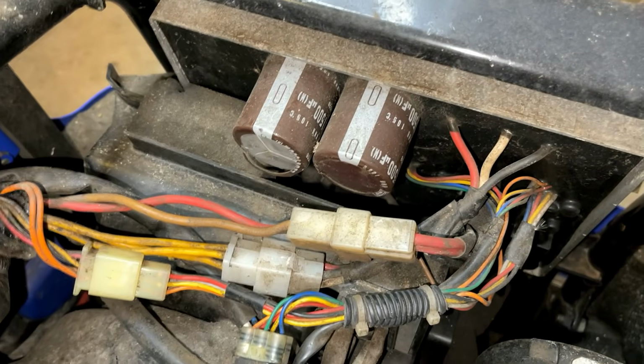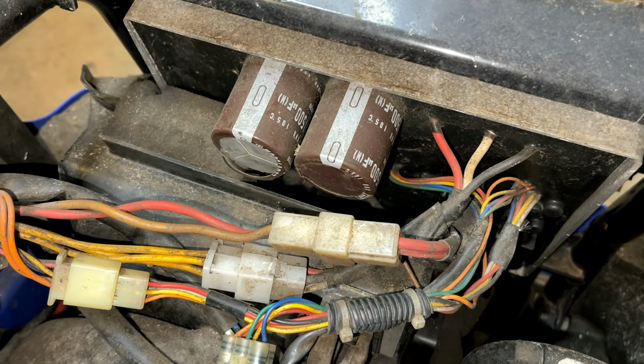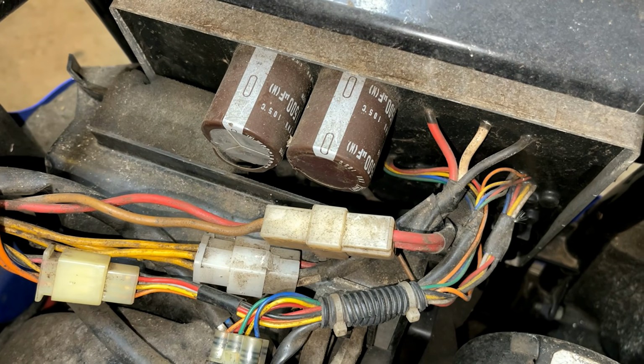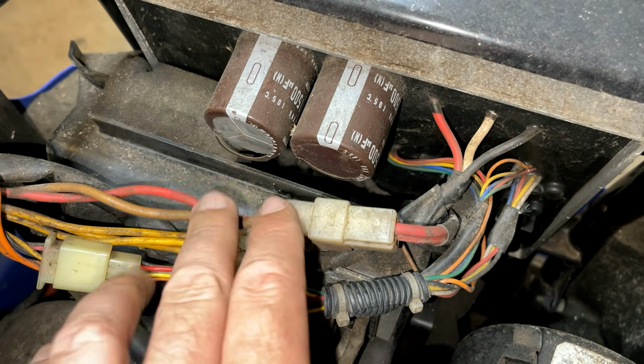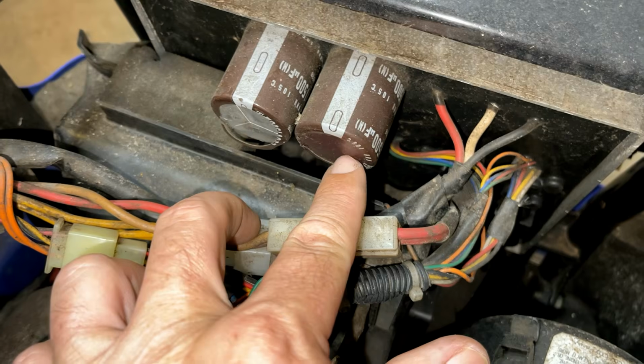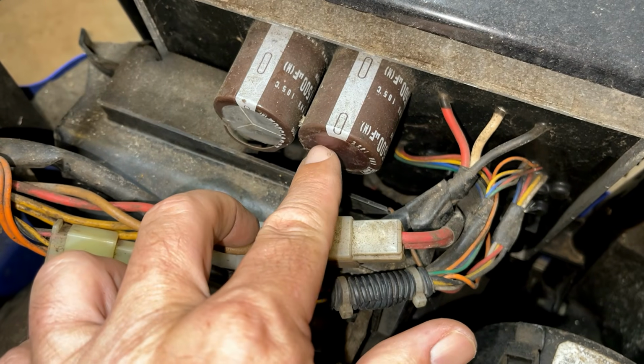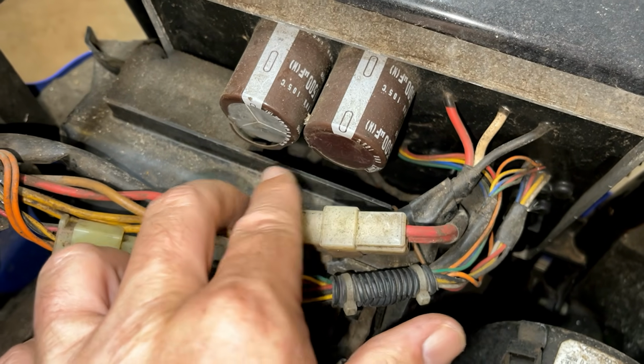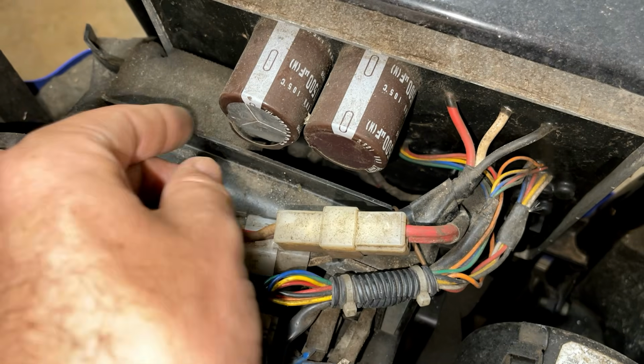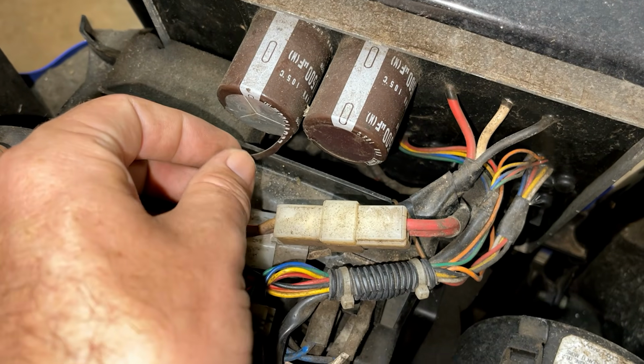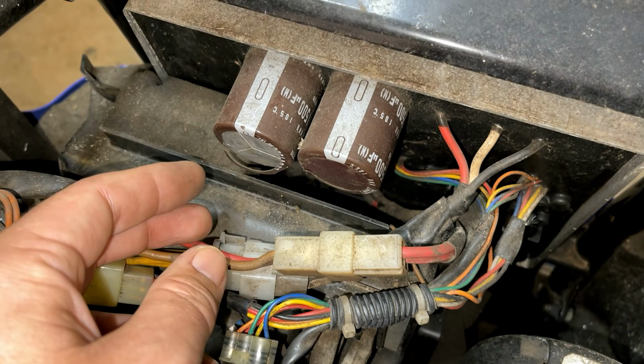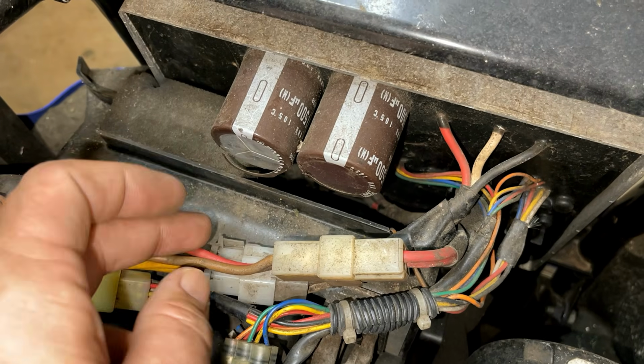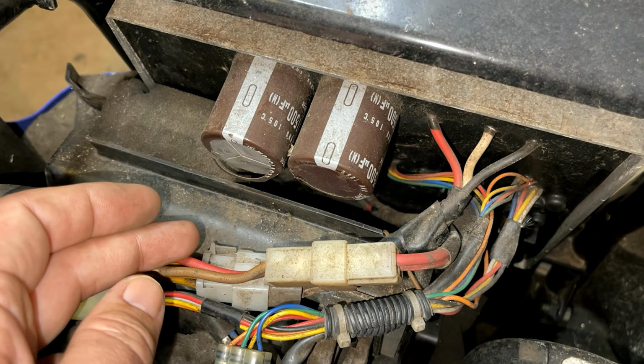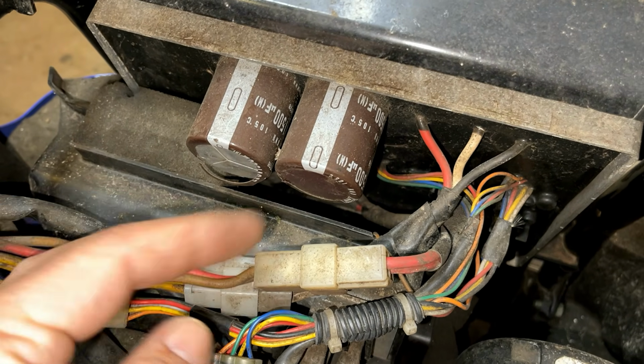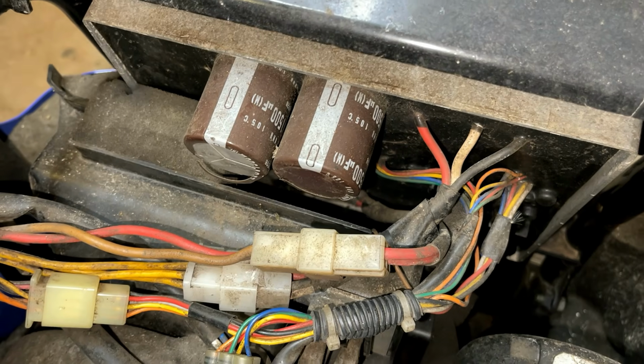Also, if you look at these capacitors on the inverter module, I think they're supposed to be identical, but the one on the right has this brown piece of plastic on top, and the left one doesn't have that. Also, this here is ripped, so if I had to guess, that's most likely the issue with the inverter, and unfortunately that's not serviceable. This whole thing is potted.